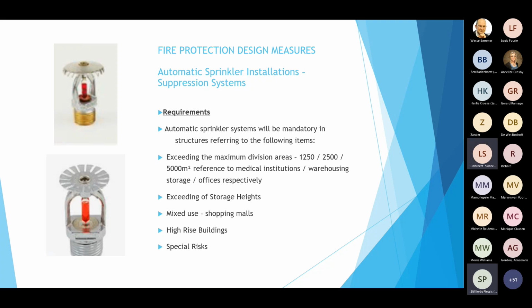The red bulb, as indicated, gives you a certain degree at which the sprinkler head activates. In the industry you get a red bulb, a green bulb, a blue bulb. This bulb is indicated for 68 degree sprinkler heads. A blue bulb would be indicated to 141 degrees. That's determined based on your other building systems and the occupancy you need to protect.